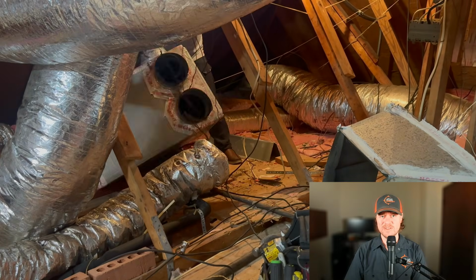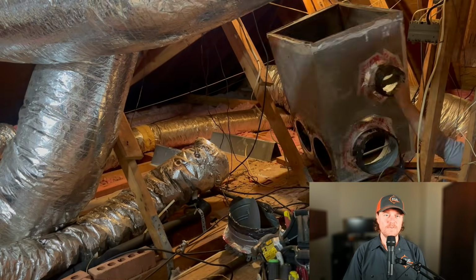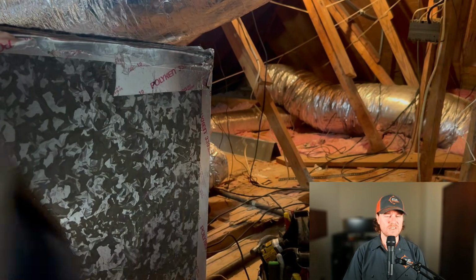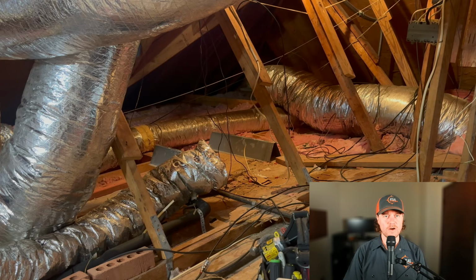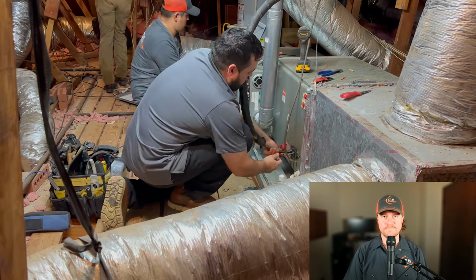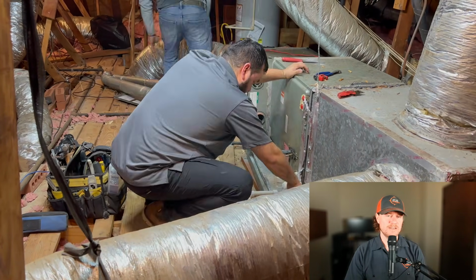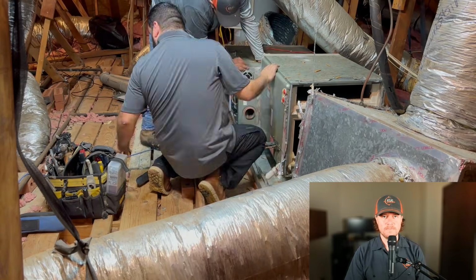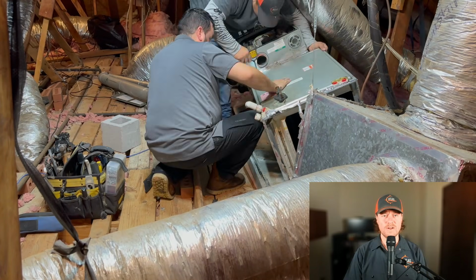The answer to that question is, it depends. For instance, if you have a single-story house and a portion of it's getting hotter or colder, and you're thinking about running a zone system to fix this problem, in other words, you're not really interested in controlling different rooms independently, but balance out hot and cold spots, I would not go down the zone route.